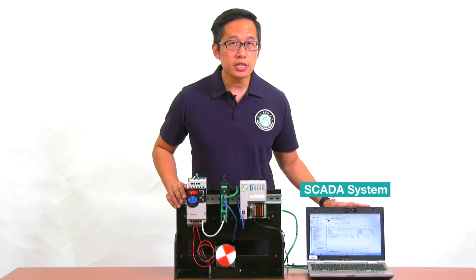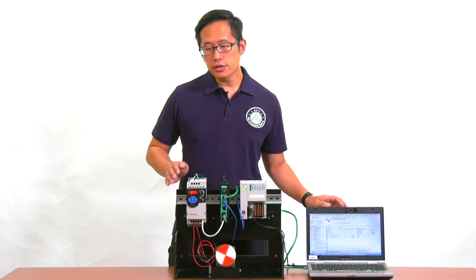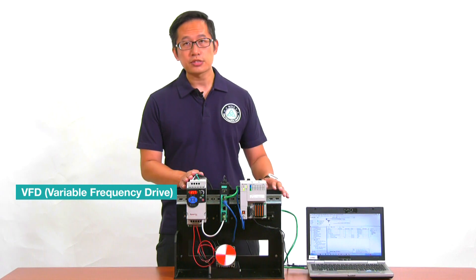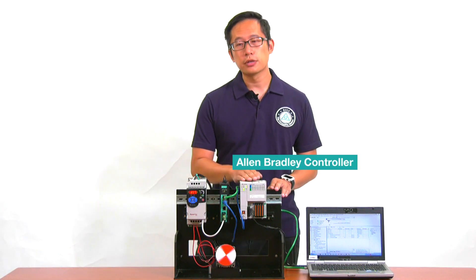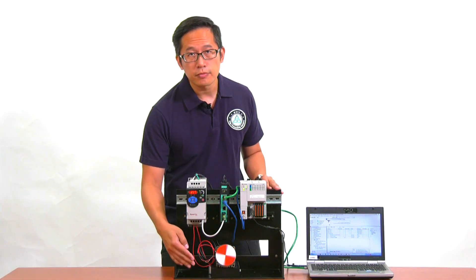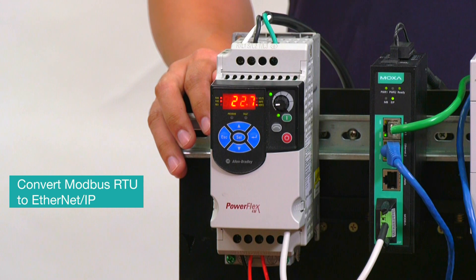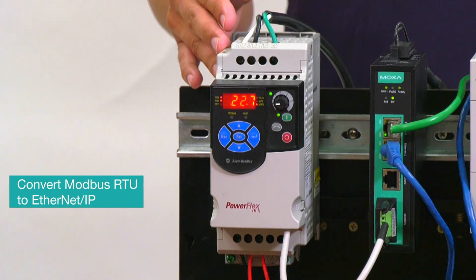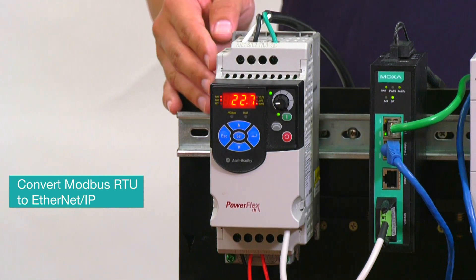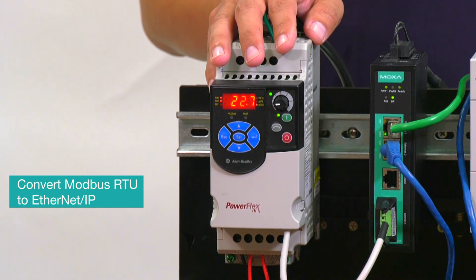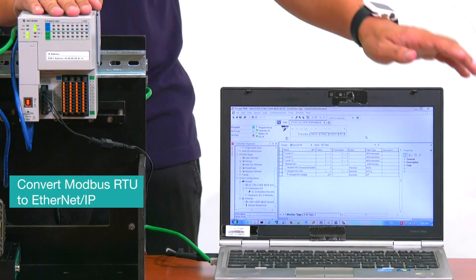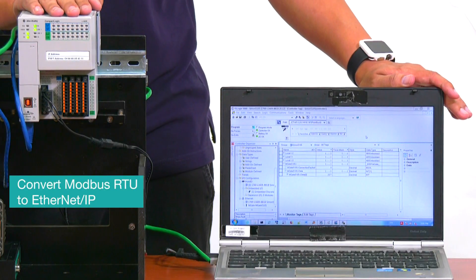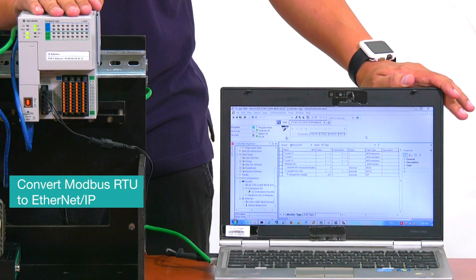Here we have a PC with SCADA software installed and a VFD that's connected to an Ethernet IP controller to control the speed of this motor. Now, to connect this VFD to your control network, you need to convert Modbus RTU protocol, which the VFD uses, to Ethernet IP protocol, which the controller and SCADA system use.